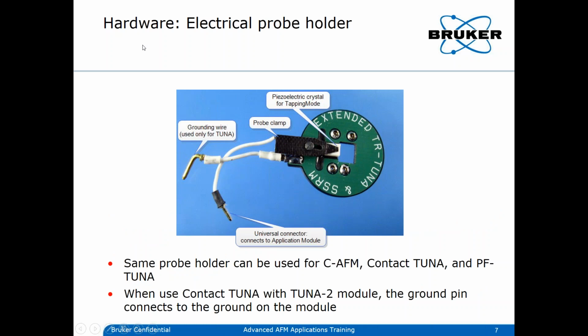For the hardware itself, you have an electrical probe holder, which can be used for TUNA, SSRM, or extended torsion. That's called the extended holder, which can be used again for torsion TUNA, standard TUNA, or SSRM. So spreading resistance measurements as well. Here you can see on this image that there's a grounding wire which is connected. Again, this would go into the ground from the module, but only for TUNA, not for PeakForce TUNA. It's not used any longer. It's not needed.